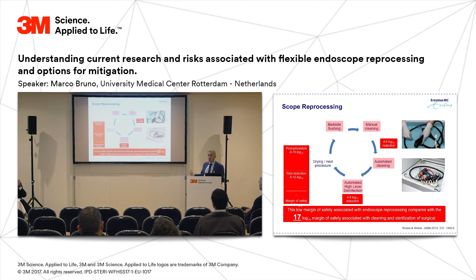You then start the automated cleaning process, the automated high-level disinfection, and again you add a 4 to 6 log10 reduction in bioburden. Now, if you add this up, this is 8 to 12 log10. If you subtract them, there's a very limited margin of safety of 0 to 2 log10. Now, if you compare that with what we have if you have a process of sterilization, it's 17 log10. So that tells you why this is such an intrinsically vulnerable process and why we have scopes that are not adequately disinfected.